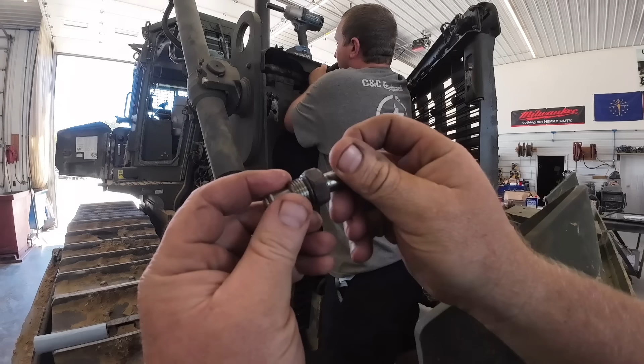There's a T-block up here, and it's also that quick drop valve I was explaining earlier. There's a magnetic coil on this valve - it looks just like this, and it could be stuck open or have some dirt in it, because the big plug was out of there when we got this thing. It had a rag stuffed in it.